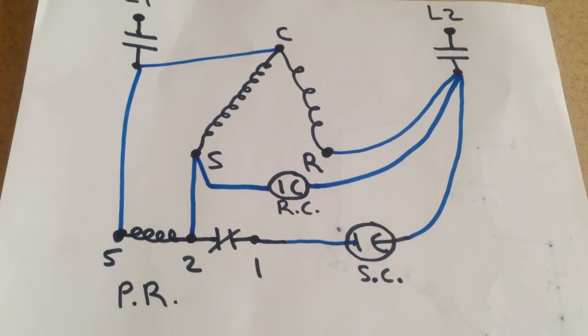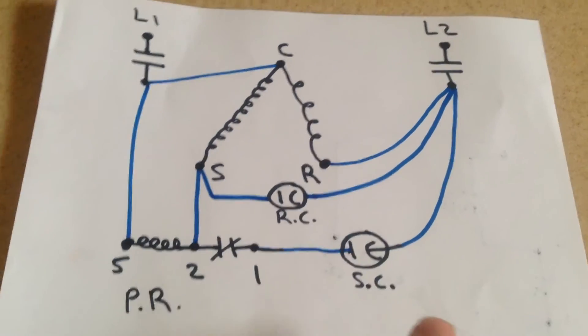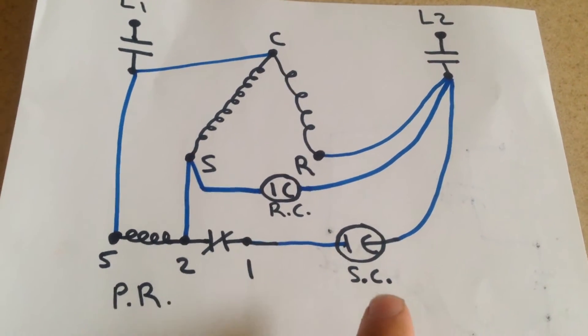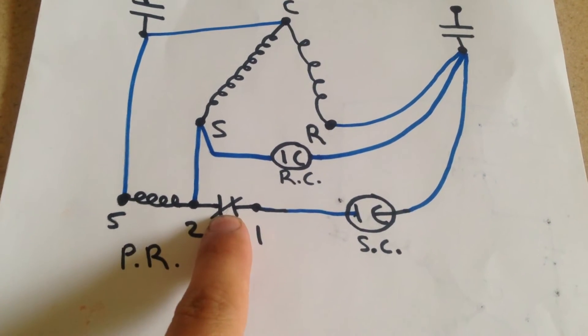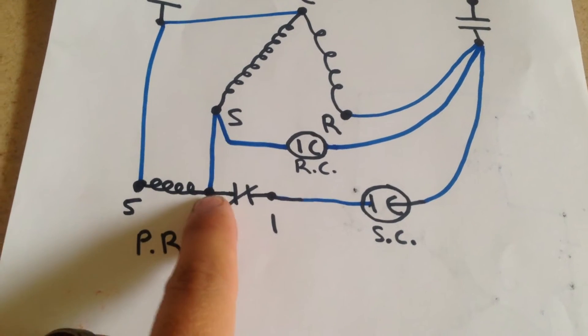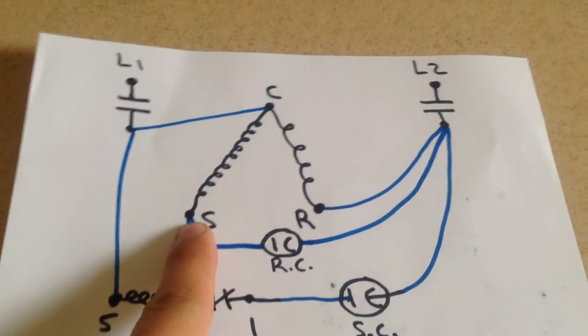But before it gets there, it's going to go in series through the start capacitor. So as you can see now, we have a path from L2 through the start capacitor from number 1 through the normally closed contact and up to the start terminal on our compressor.